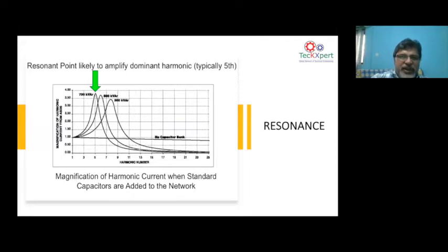That means if in your office or in your factory you have UPS, VFDs, or lighting loads, you are having 3rd, 5th, 7th harmonics, then you have to ensure that whenever your capacitor bank is installed, you size it correctly so that it does not cause resonance at lower frequencies. Go to the next.